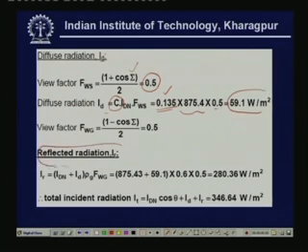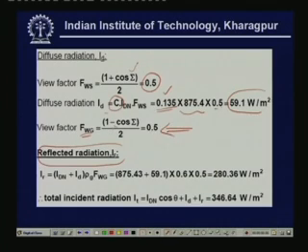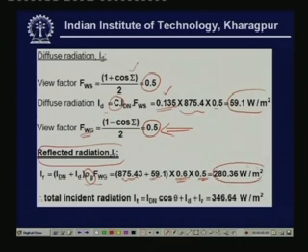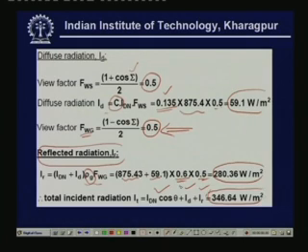Next we find the reflected radiation. The view factor between the ground and wall, F_WG = (1 - cos(epsilon))/2 = 0.5. The reflected radiation from the ground equals (I_DN + I_diffuse) × rho_G × F_WG, where rho_G = 0.6 and F_WG = 0.5. Substituting I_DN and I_diffuse, the reflected radiation works out to be 280.36 W/m². The total incident radiation is the sum of direct, diffuse, and reflected radiation: 346.64 W/m².